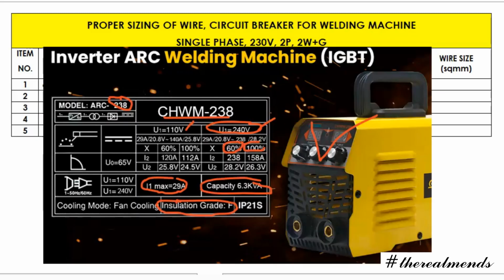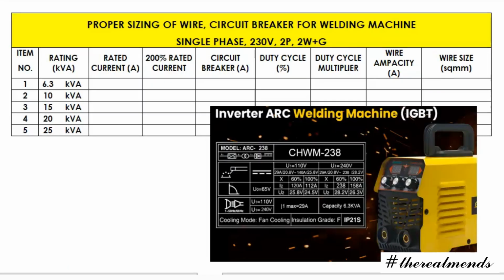Okay, so after we read the nameplate, meron tayong sample ng para siyang load schedule. Then meron tayong item. So assuming na meron tayong limang welding machines na ginagamit. So yung kVA rating 6.3. Ito yun, 6.3. And then 10 kVA, 15 kVA, 20 kVA, and then 25 kVA. So assume na itong welding machines natin is individual ang gamit. And then we have one column, rated current, and then 200% of the rated current, circuit breaker, duty cycle multiplier, and then wire ampacity, also with the wire size. But for this time we'll just focus only sa circuit breaker, and then next is the wire sizing.